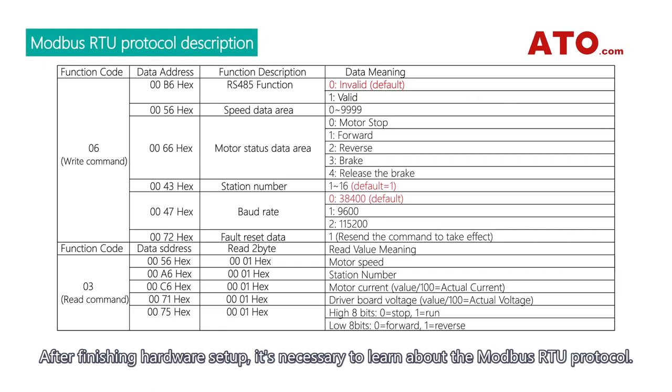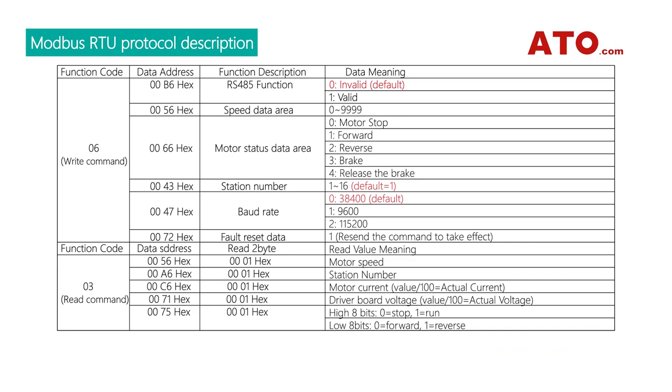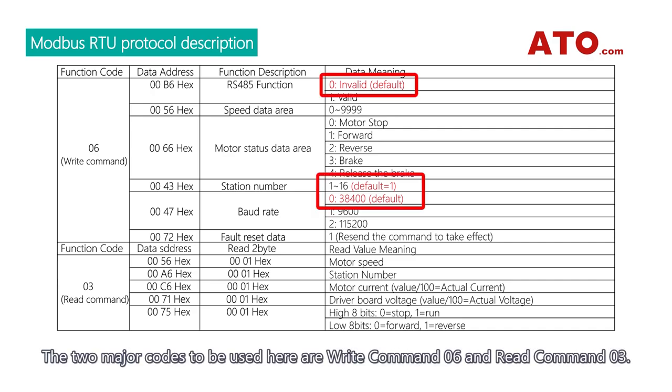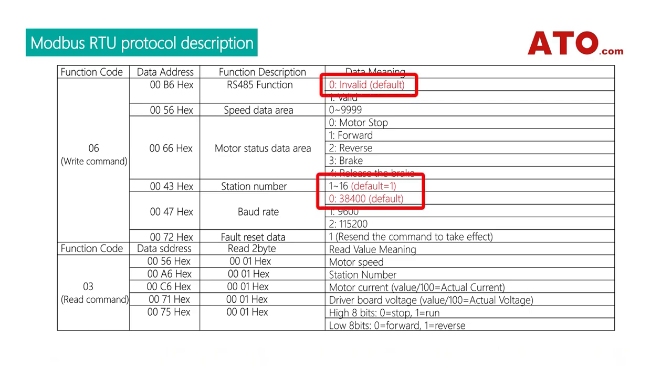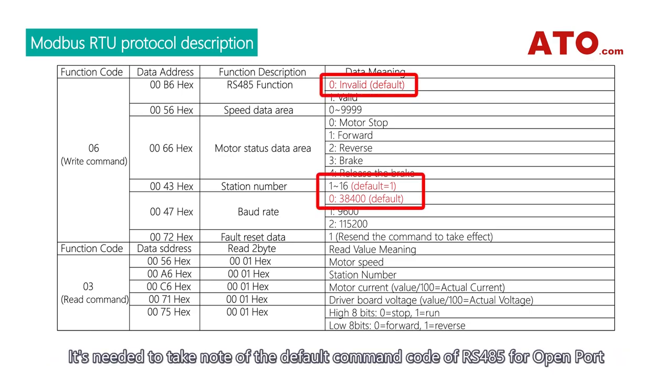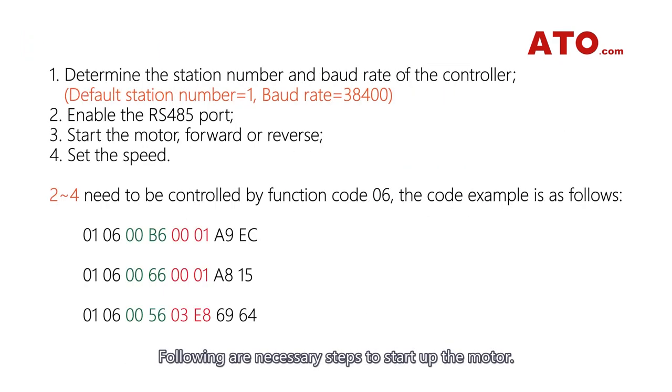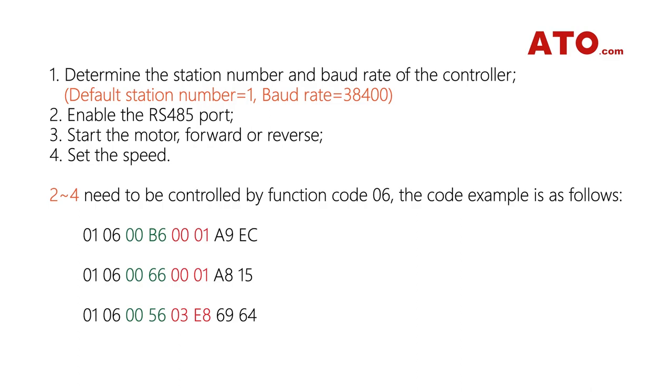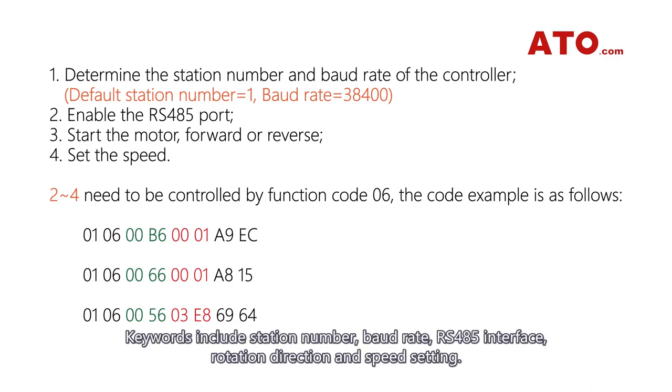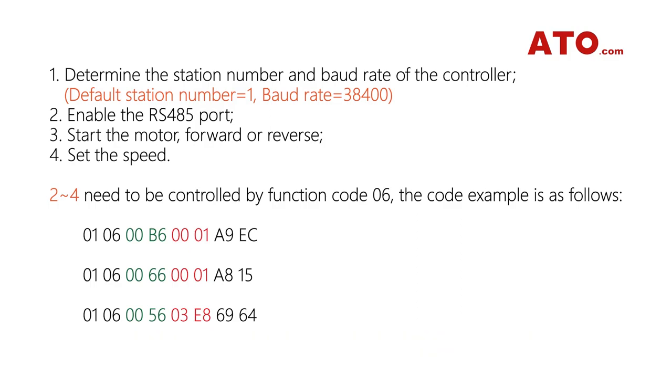The two major codes to be used here are write command 06 and read command 03. It's needed to take note of the default command code of RS485 for open port, as well as the station number and baud rate of the controller. Following are necessary steps to start up the motor. Keywords include station number, baud rate, RS485 interface, rotation direction, and speed setting.